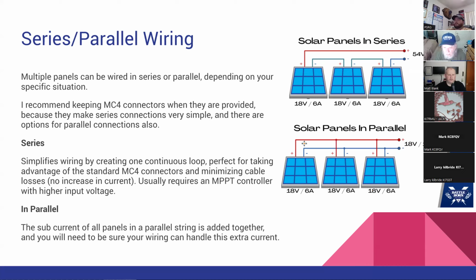You can run each panel into its own circuit breaker and into a bus. There's lots of ways to do that, but keep in mind that however many you add, you have another set of wiring, and your total wiring going to the charge controller current is going to increase. So you need to make sure that's big enough to handle it.